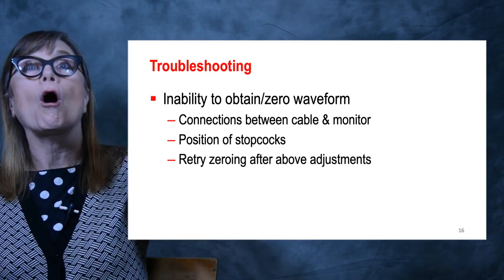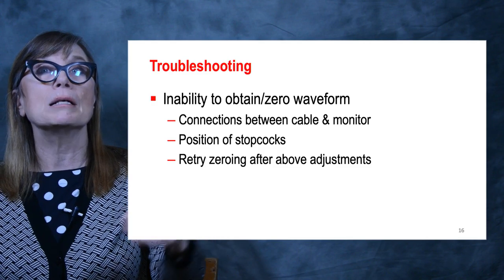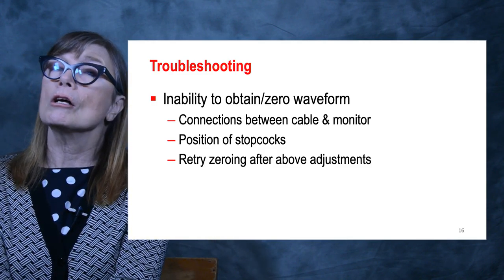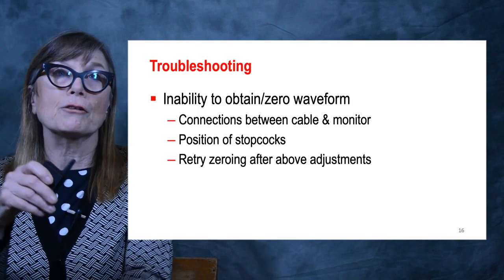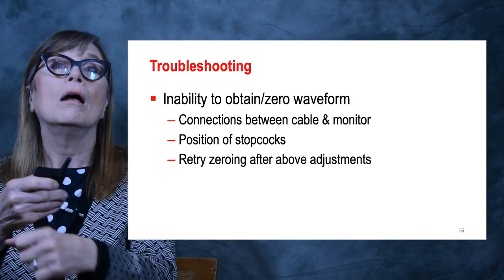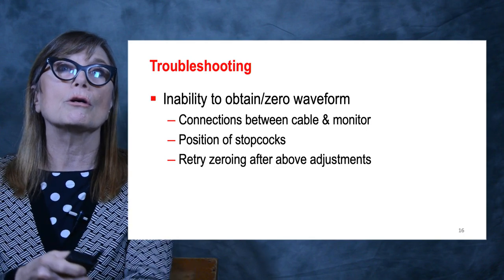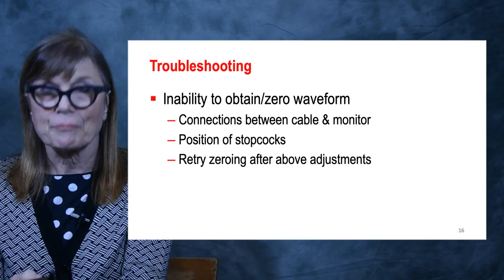Okay, now the other thing is if I can't obtain a zero waveform, something is wrong with the stopcock positioning. Remember, off to the patient, open to atmosphere. And also make sure all your connections between the cable and the monitor, the transducer pigtail, the cable and the monitor, make sure those are all tight and appropriate.